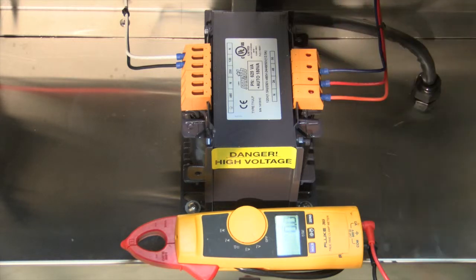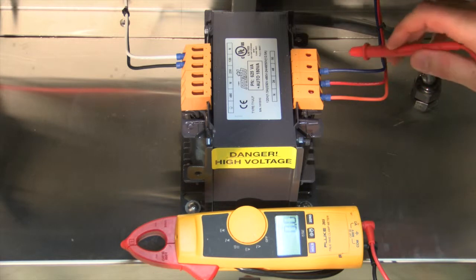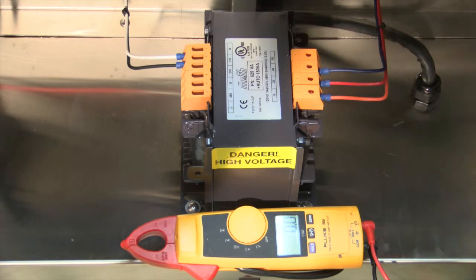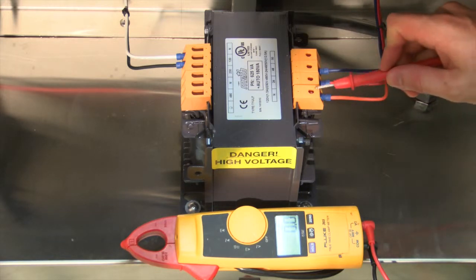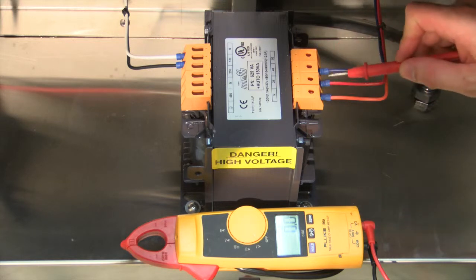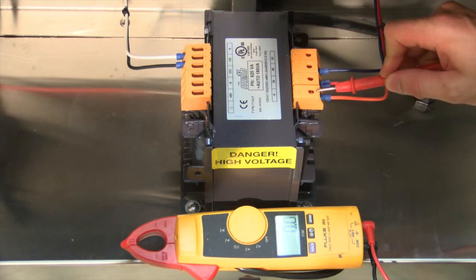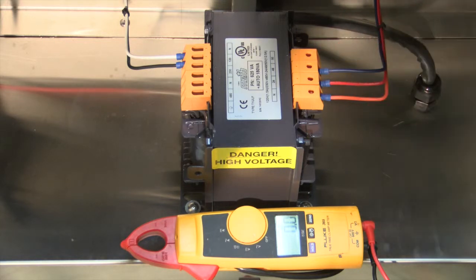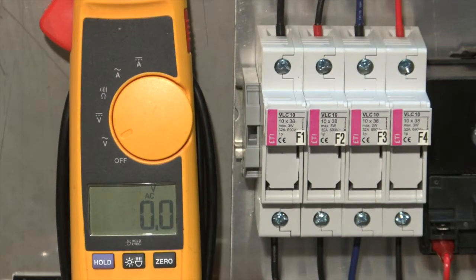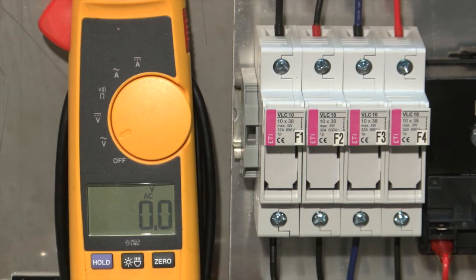As you can see, when the transformer is drawing, you cannot get an accurate volt reading to ground. When reading the secondary side of the transformer, always use the secondary neutral to take your power readings. The same rules apply when looking at the fuse block.